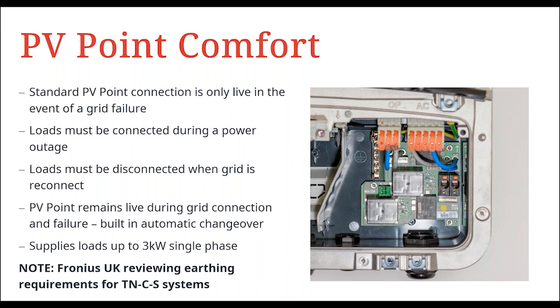One thing to bear in mind is we are currently reviewing the earthing requirements for the UK and Ireland. Obviously, we have a lot of TNCS systems within both these countries, and as a result, we need to make sure that we have the correct earthing arrangement set up. So we're expecting a small delay on the start of sales of this device while we just confirm all those settings. If you have a TT system, then there's nothing to worry about there.